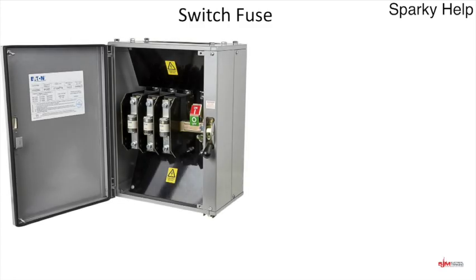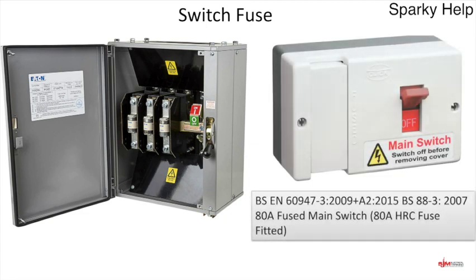Or you could have a fused switch. Here's a fused switch — this is Eaton, formerly MEM. When you throw this switch, the fuses in the centre actually make the switching process. You can put BS88 type fuses in there of various types and sizes up to the rating of the switch — so if this is a 100 amp switch, up to 100 amp. Or you can have a BS88-3 80 amp fused main switch installed within an installation. Remember, these will be overcurrent protected devices, so under fault conditions these particular devices will switch off.